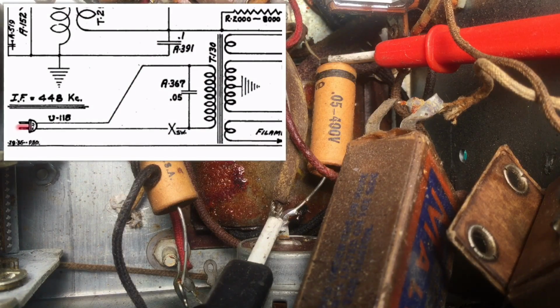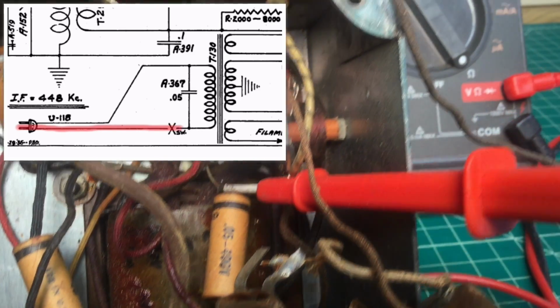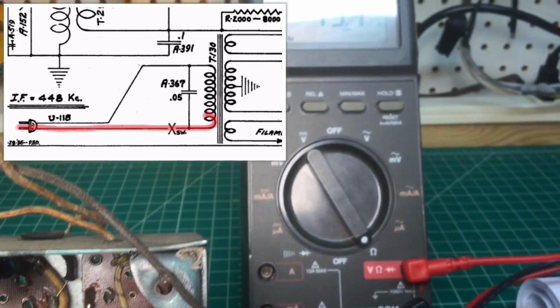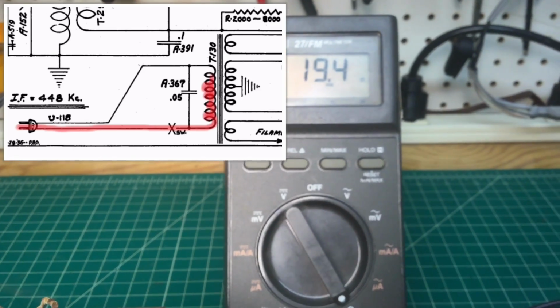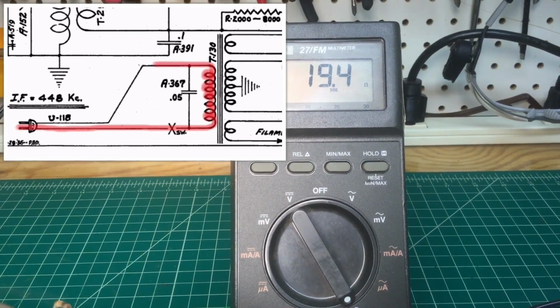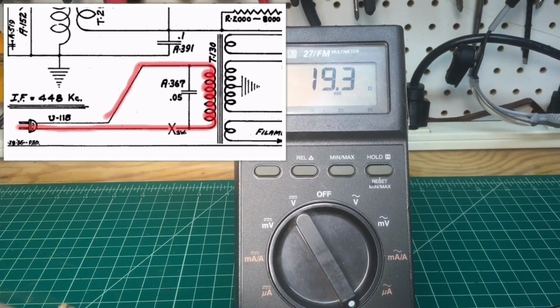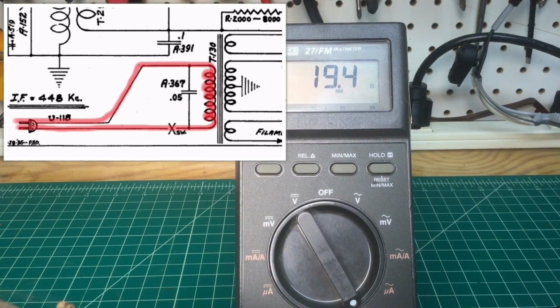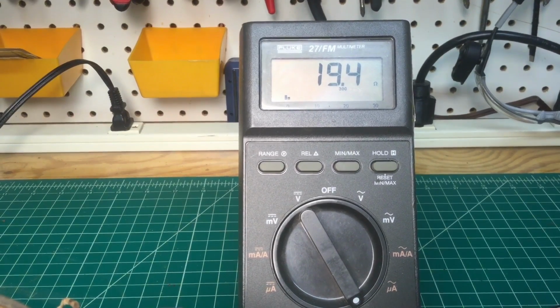The meter lead's hooked up, and you can follow along here in the picture-in-picture, see where I'm at. Everything's looking good. I've got about 19 ohms of DC resistance here on the primary side, and I did verify the switch is working as well. So I think we're in pretty good shape here. We'll have to bring it up on the variac, but let's move along to the secondary side.